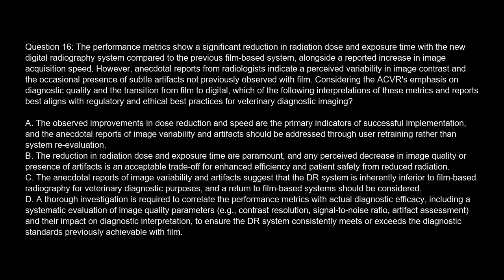Option D. A thorough investigation is required to correlate the performance metrics with actual diagnostic efficacy, including a systematic evaluation of image quality parameters, e.g., contrast resolution, signal-to-noise ratio, artifact assessment, and their impact on diagnostic interpretation to ensure the DR system consistently meets or exceeds the diagnostic standards previously achievable with film.